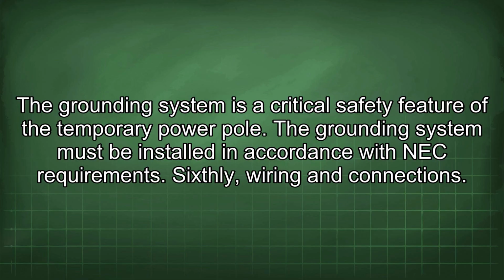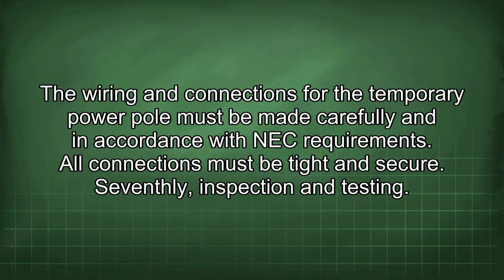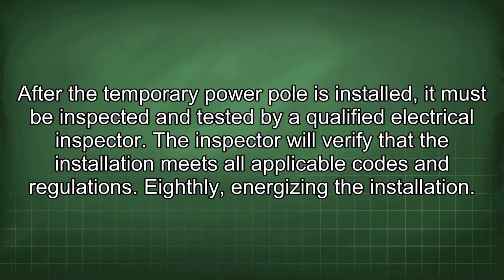Sixthly, wiring and connections. The wiring and connections for the temporary power pole must be made carefully and in accordance with NEC requirements. All connections must be tight and secure. Seventhly, inspection and testing. After the temporary power pole is installed, it must be inspected and tested by a qualified electrical inspector. The inspector will verify that the installation meets all applicable codes and regulations.